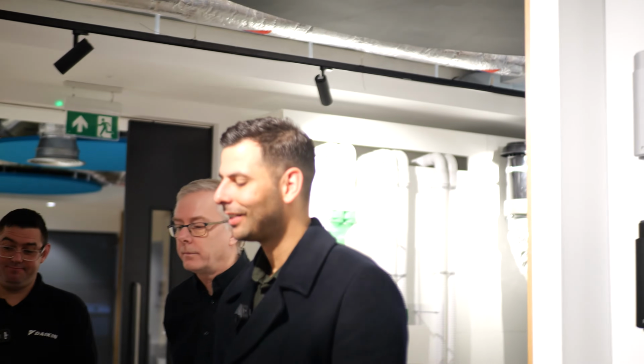When we talk about heat pumps, we're also talking about minimum water volume in the system and minimum flow rates. This gets rid of the minimum flow rate issue because it's just the heat pump circling around the buffer, and we get rid of the minimum water volume issue because it's already all there, maintained at 37 degrees.